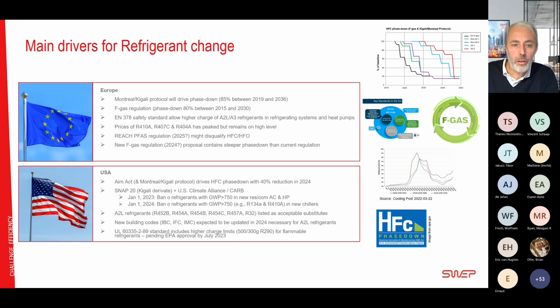Also interesting, we have the UL 60335-2-89 standard that includes higher charge limits for flammable refrigerants. This is in place, but it's pending the EPA approval, July 2023, and it will actually allow up to 500 grams of propane or R290 for commercial refrigeration.